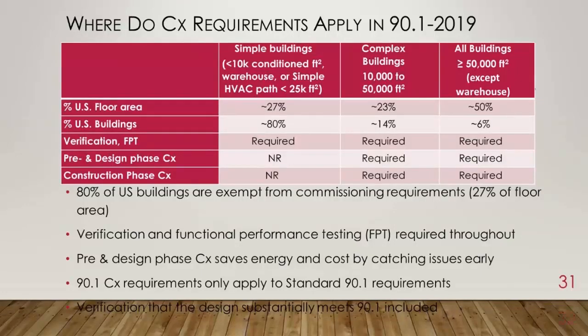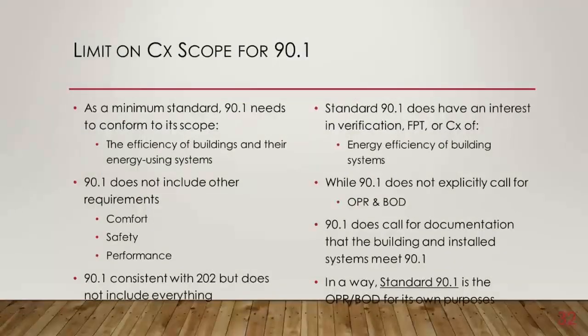Okay, moving on. So there are some limits on the commissioning scope. Again, the scope of 90.1 is energy efficiency requirements. So we can't put in place commissioning requirements in 90.1 that go above and beyond those energy efficiency requirements. There are certainly other things: comfort, safety, performance, maybe even moisture penetration. I used that example earlier.